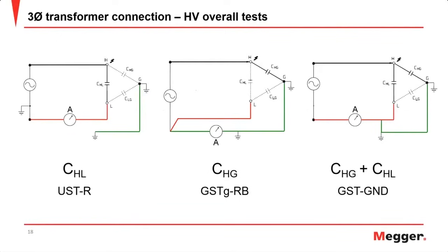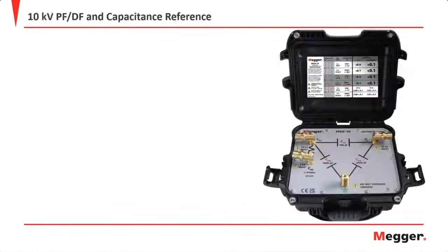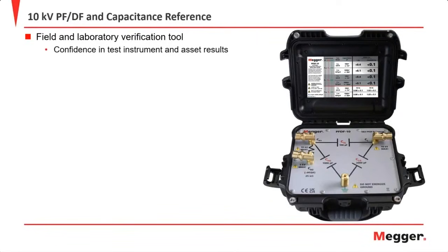But if they do not add up, or if you have a question about any of your power factor measurements, whether they're capacitance or power factor itself, you can have a reference to verify that your instrument is working properly. And what we have is an accessory that gives you the field verification capabilities to verify that entire insulation measurement system. Sometimes you may use a capacitor to verify your power factor measurements, but your capacitor is only going to get you your UST-R measurements, and it's not going to verify the functionality of that ground channel. And with a device like the PFDF10, you can connect your high voltage, your measure red, and your ground measurements and confirm all aspects of your insulation measurement system.